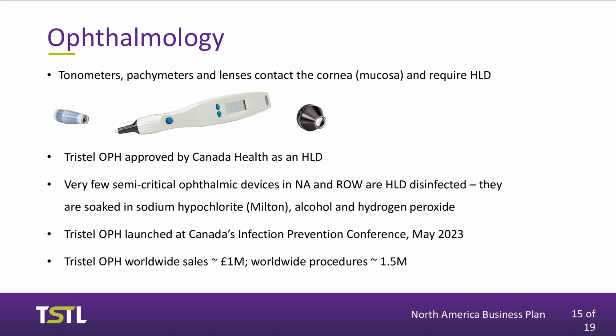The middle instrument is a pachymeter, and the lens on the right-hand side. Each one of these instruments comes into contact with the cornea, which is a mucosa. And if we go back to that Spalding classification, they're semi-critical devices and they require high-level disinfection. But around the world, there are no high-level disinfectants, apart from Duo, where it's been registered and is in widespread use, available for ophthalmic devices. Canada Health was approached maybe 2.5 years ago. We sought approval from them as a high-level disinfectant, and it was granted. And we have now launched the product in conjunction with our partner, and it is receiving a very, very strong reaction from the infection prevention, optometrist and ophthalmologist community in the country.